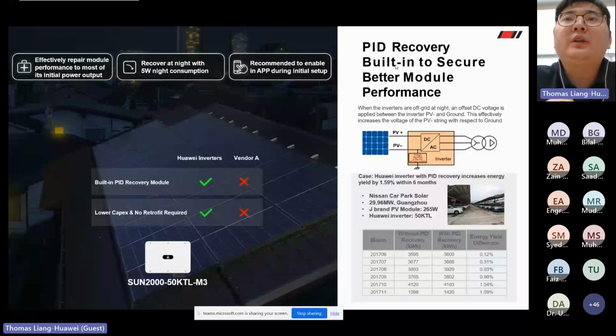So for the Huawei inverter, we have the built-in PID recover module inside the inverter. When the inverter is off grid at night, an offset DC voltage will be applied between the inverter PV negative and ground. This will increase the voltage of the PV negative string with respect to ground. With this function, you can help to recover from the harm of PID issues.